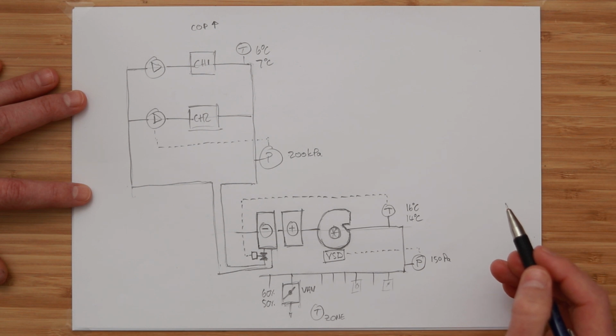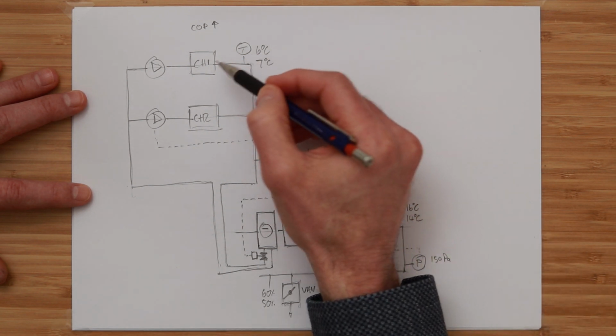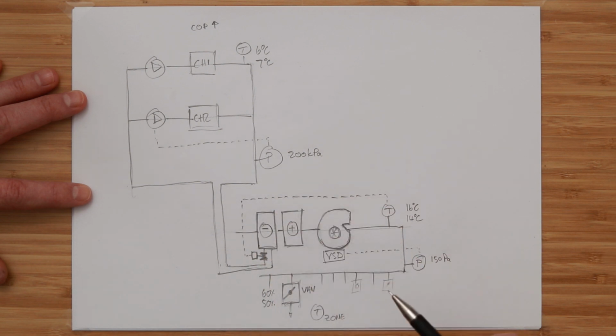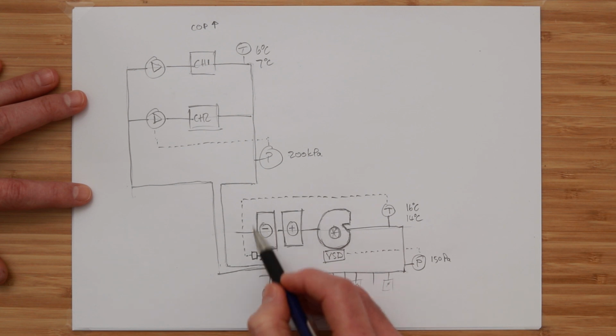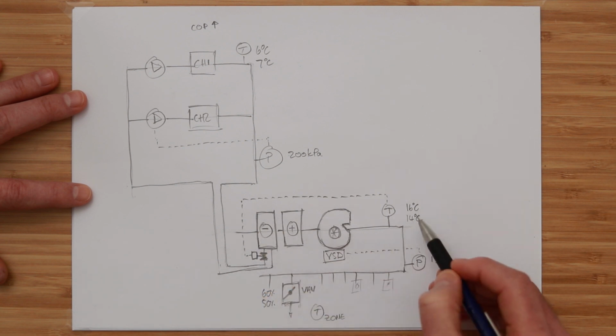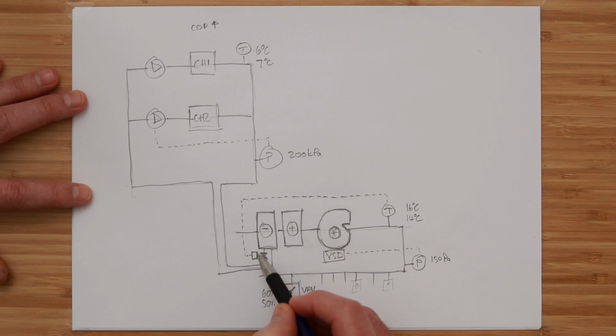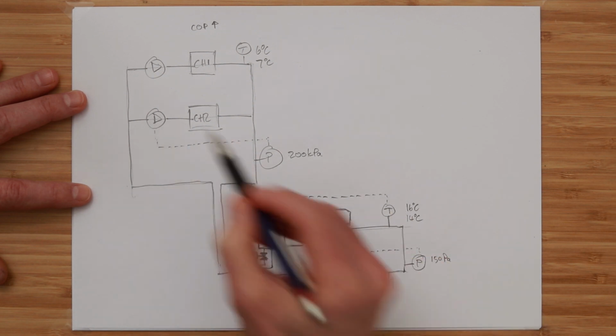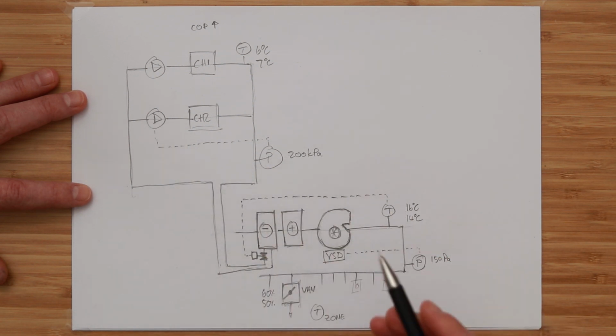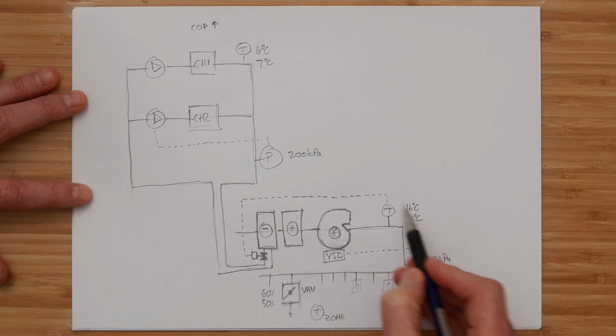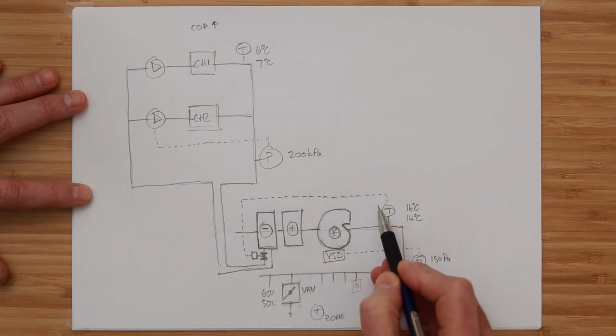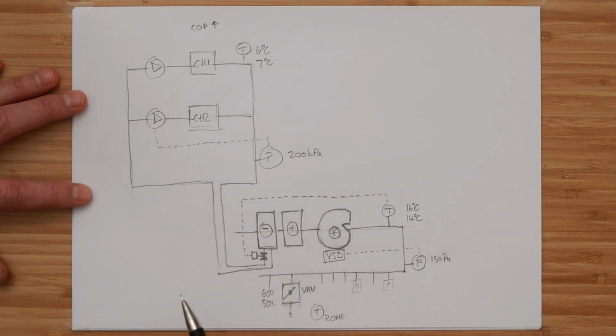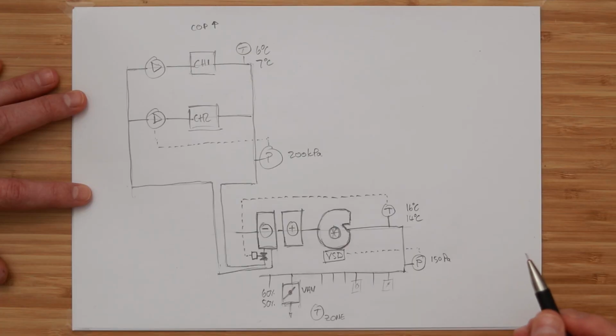of the chiller increases. Now again, what happens is as we do that, slightly warmer temperature comes through the chilled water system. That warmer temperature comes through here, there's less cooling capacity available to us, and this temperature comes up a little bit, the cooling valve opens to compensate, and the speed drive increases to make up for more pressure. So where this optimization strategy here negatively impacted on the pumps, the same thing happens as we optimize the chiller's COP, it negatively impacts on the pumps. So just put that to one side as well for a second.